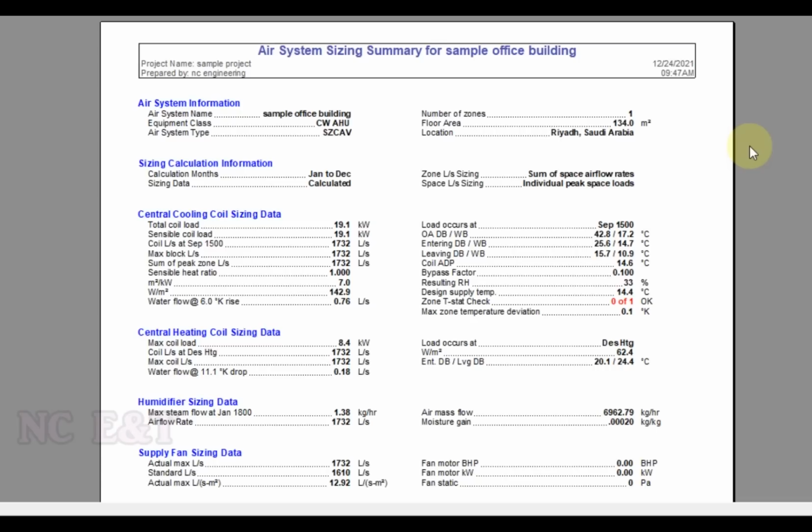Then you need to select the timing of the system. If you are going for residential purpose, you need load calculation for 24 hours. If you are going to use this building for office use, there is some specific time for which you will use the building. So for that you need to make a schedule for people, for light, for equipment and for thermostat.